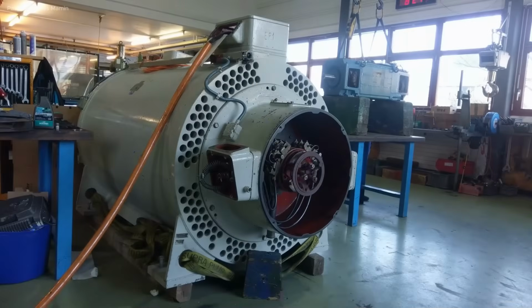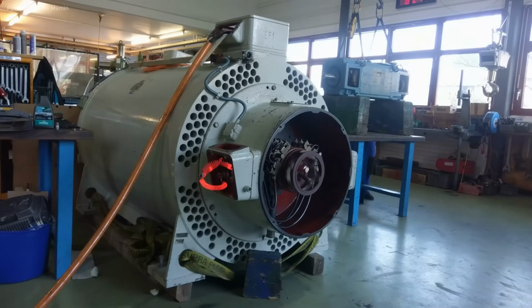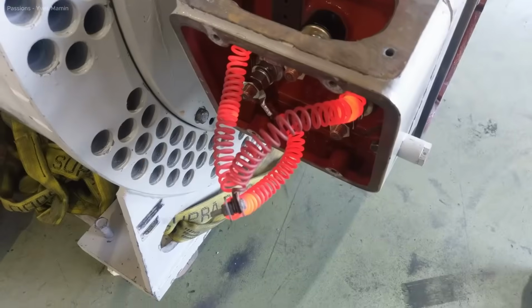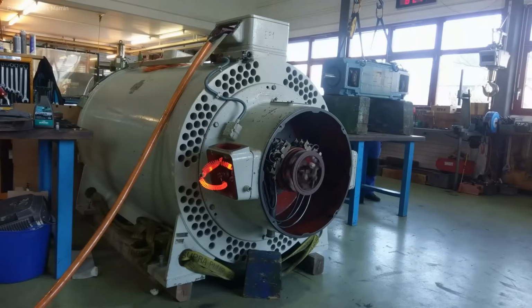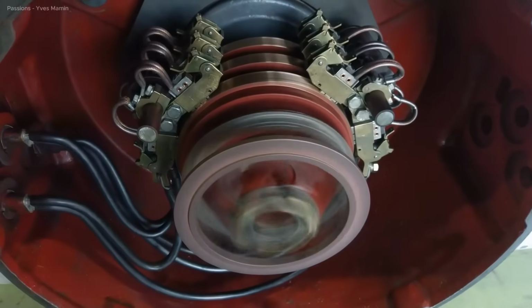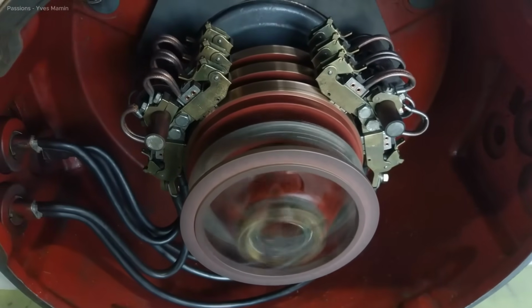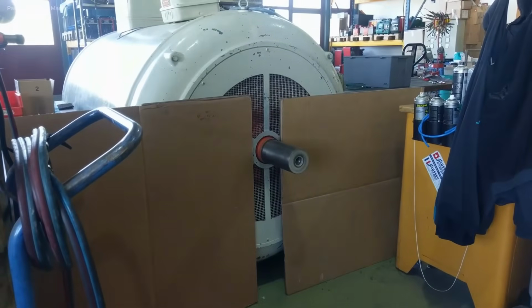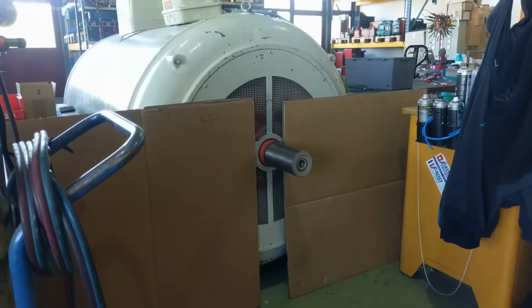The 6 kV, 3-phase, 50 Hz, 500 kW slip ring motor was restarted under 800 volts. Rotor rings were short-circuited through fixed resistors to control inrush current, ensuring safe and smooth acceleration during post-revision workshop tests for cement industry application.